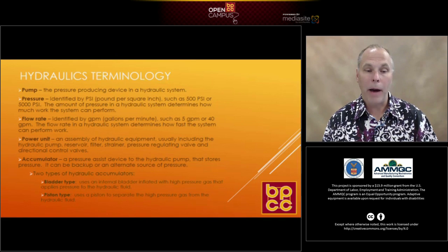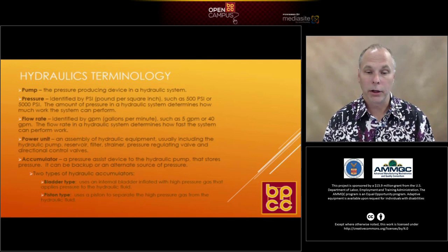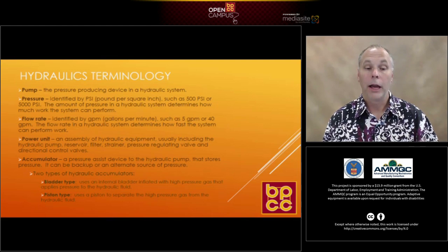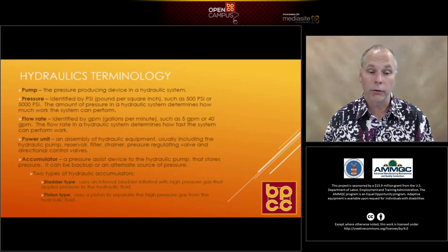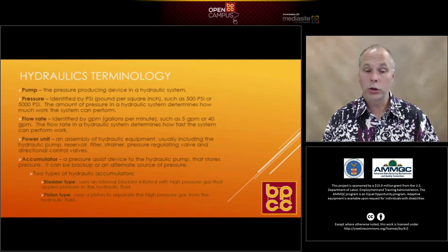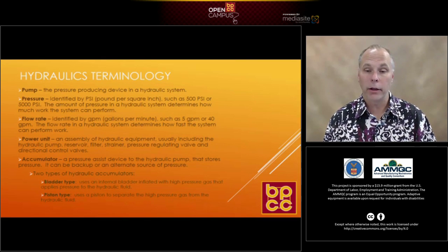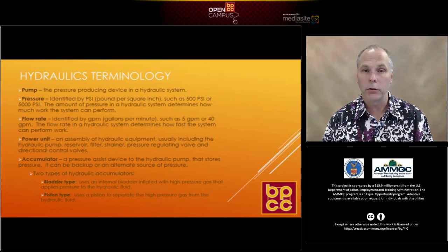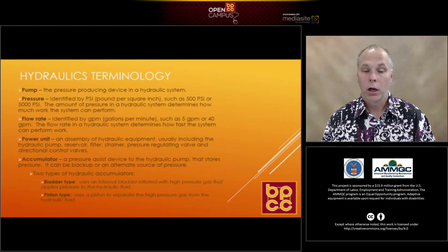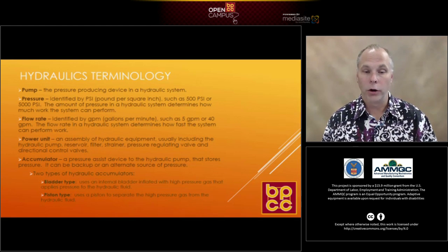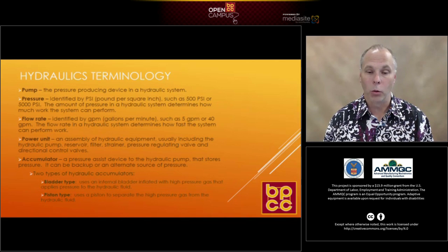Sometimes they call it a power unit. It's the assembly of hydraulic equipment, usually including a hydraulic pump, a reservoir that holds the hydraulic fluid, filters, strainers, pressure gauging regulation, valves that keep the pressure at certain levels, and even directional control valves. Directional control valves are used to push hydraulic fluid under pressure in certain directions to actually do work.